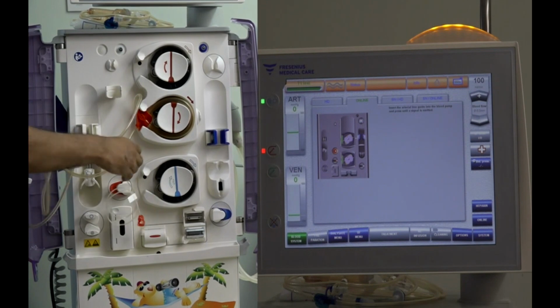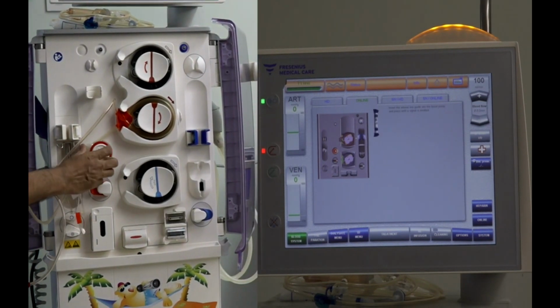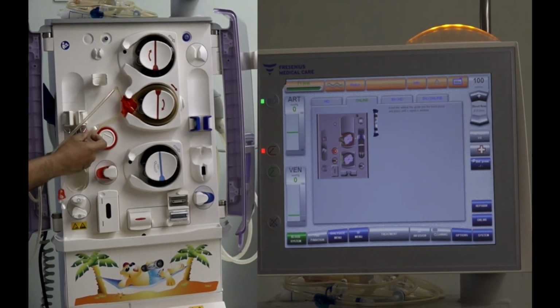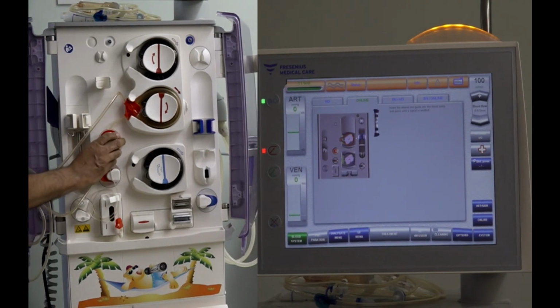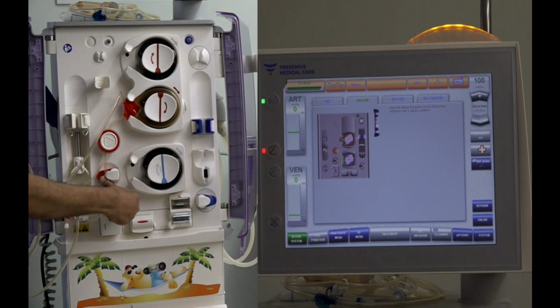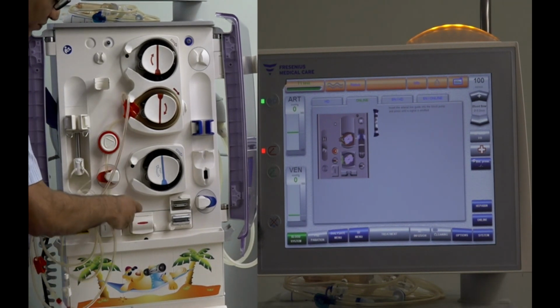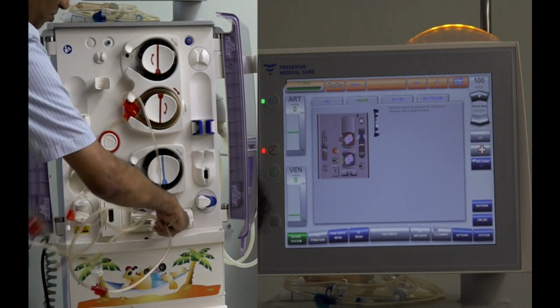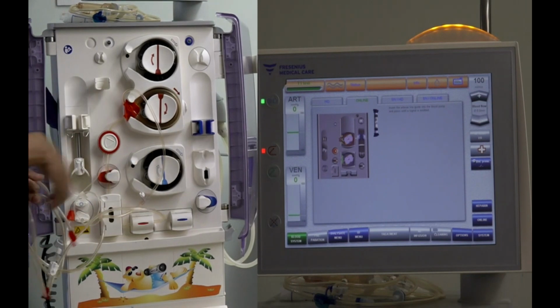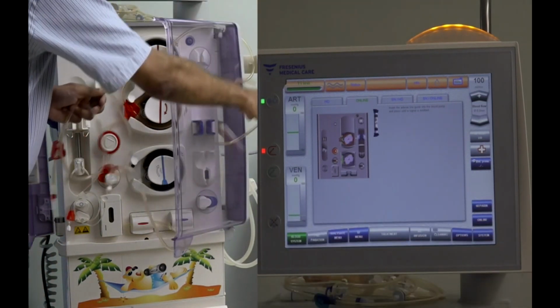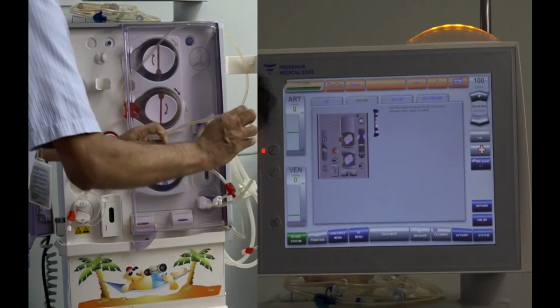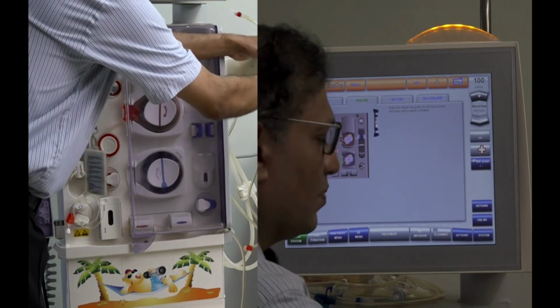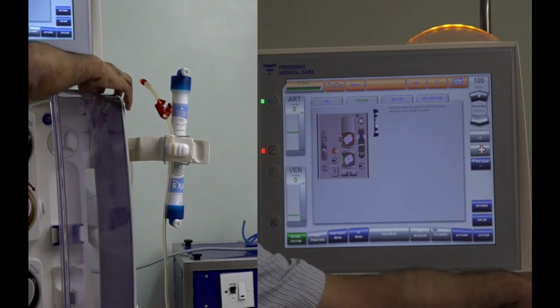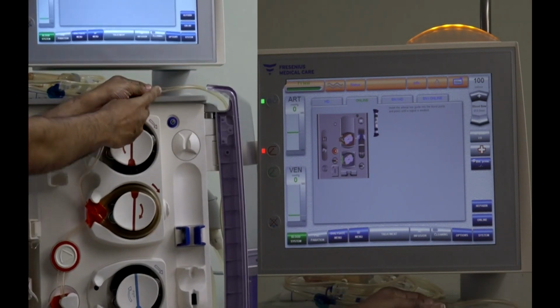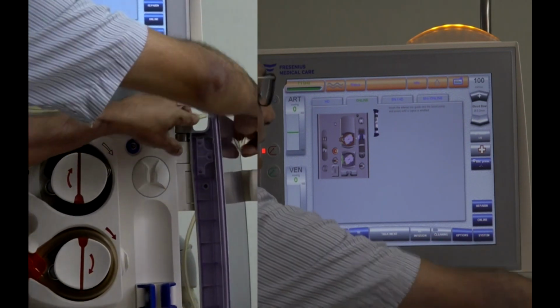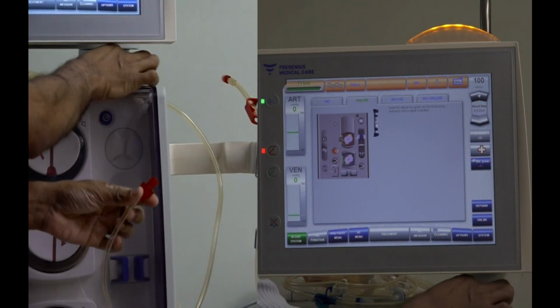There, did you hear that little sound? That was the sensor engaging with the spike on the machine, and consequently this dome opens, which allows me to load the pressure pod into it. So I've loaded the pressure pod. This is the arterial line clamp. This is the blood volume monitor. And this is the blood temperature monitor. The blood line has a port here which is for pre-filter delivery of substitution fluid, and then it goes to the dialyzer just as in conventional hemodialysis.